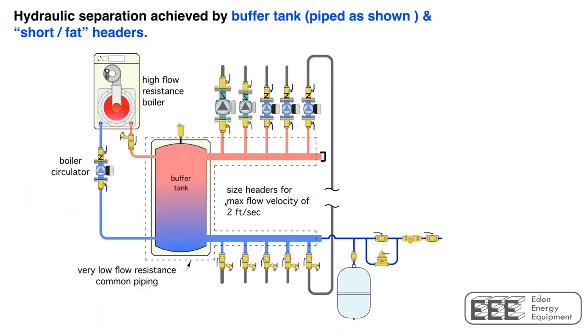A buffer tank — whether piped in a four-pipe arrangement, which is shown here — last week we talked about two-pipe and three-pipe as well. All three piping configurations — four-pipe, three-pipe, two-pipe — can provide hydraulic separation. The key is keeping the flow resistance through what we call the common piping as low as possible. I have it outlined here with a dashed line: anything inside that dashed line is part of the common piping. Keep the flow resistance of the common piping as low as possible and you'll have a high degree of hydraulic separation.